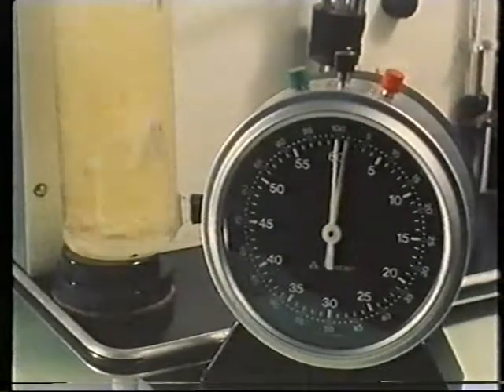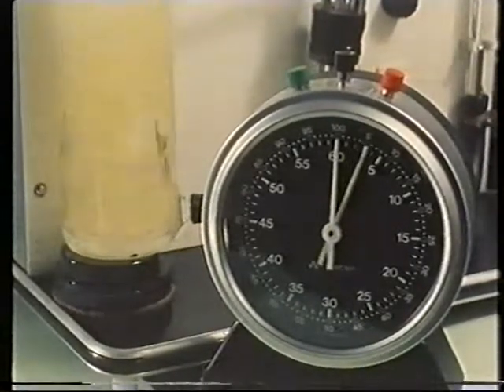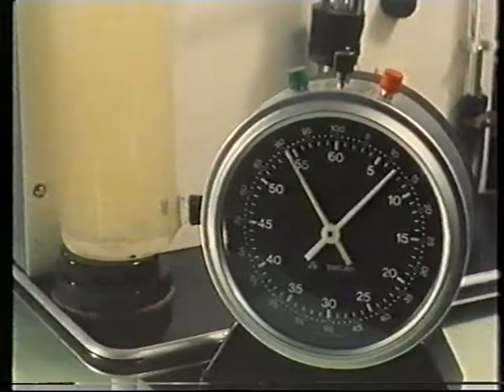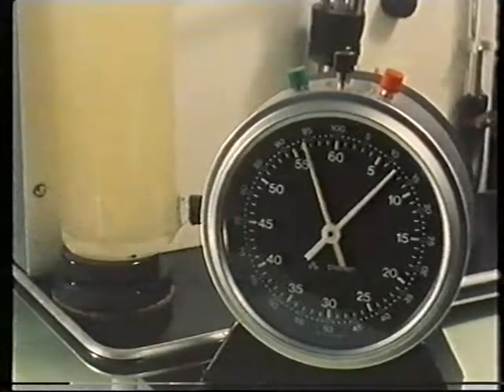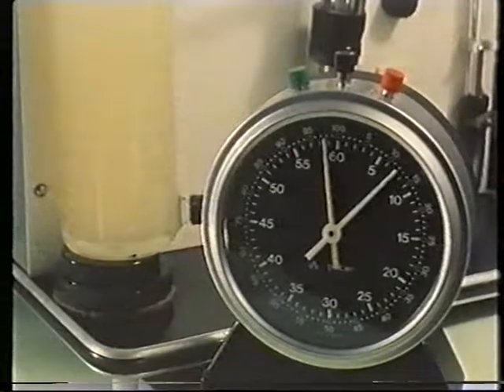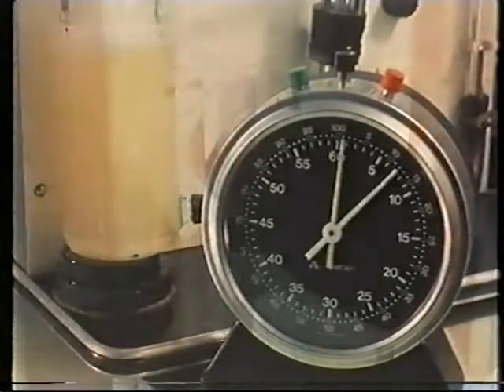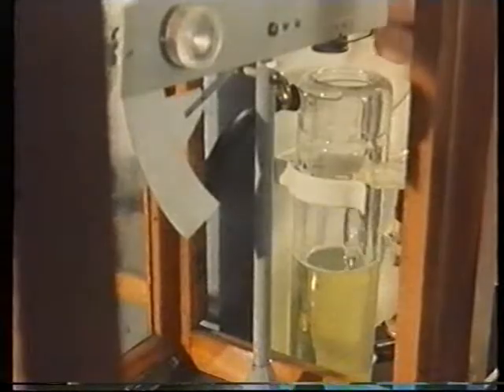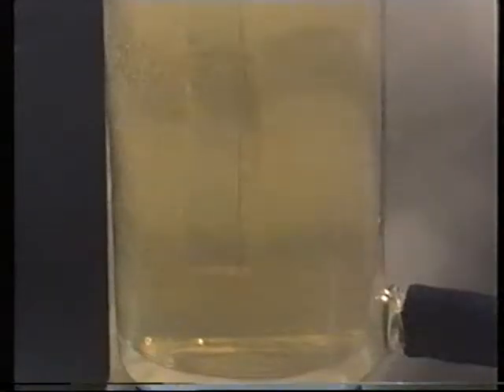The ability of an oil to release entrained air is measured during an air release test. Compressed air is blown through preheated oil. After seven minutes, the airflow is stopped. The time taken for the volume of entrained air to be reduced is recorded.